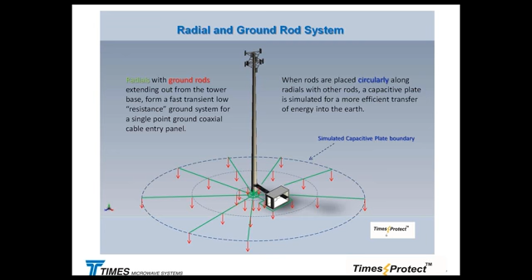And in this case, we are showing nice homogeneous type soil, so the whole ground rod is deployed effectively. But very seldom do you have a homogeneous soil. Homogeneous meaning that all the layers over the 2 meters of the length of the grounding rod are identical, okay? So you've got the shunting capabilities straight across that rod. Very frequently we are going to have a layer. We're going to have some top layer, we're going to have a clay, we're going to have sand, we might have whatever. And the conductivity of that soil is going to vary with the number of conductive ions being washed and the composition of material, of acidity of the soil.